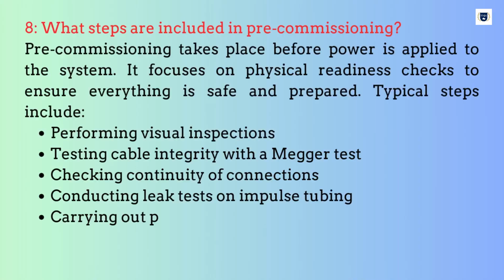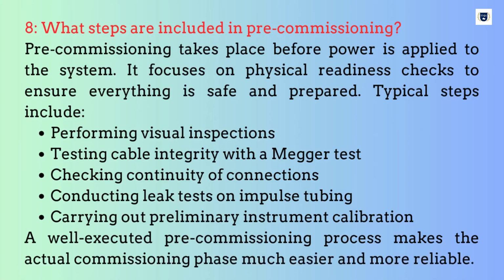What steps are included in pre-commissioning? Pre-commissioning takes place before power is applied to the system. It focuses on physical readiness checks to ensure everything is safe and prepared. Typical steps include performing visual inspections, testing cable integrity with a Megger test, checking continuity of connections, conducting leak tests on impulse tubing, carrying out preliminary instrument calibration. A well-executed pre-commissioning process makes the actual commissioning phase much easier and more reliable.